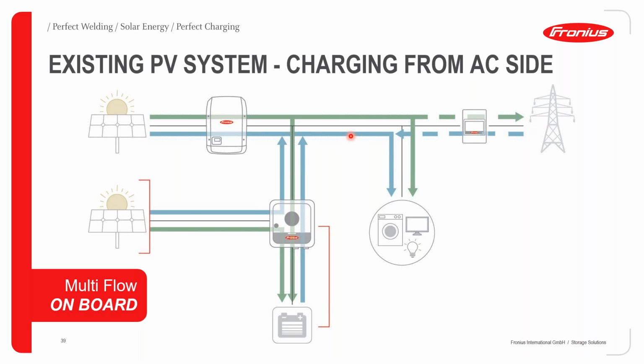So there are some instances where time of use tariffs, depending on the grid operator, are quite favorable, especially maybe in the early morning hours from 2 a.m. all the way to 5 a.m. Some users might decide that if the battery state of charge is below a certain threshold, they can use their grid supply. Also, depending on the time of the year, the season, you may realize you are going to have overcast conditions for the next 1 or 2 weeks. In those scenarios, you can use the grid through the Gen 24 inverter to ensure that the batteries always have a minimum state of charge using grid power.